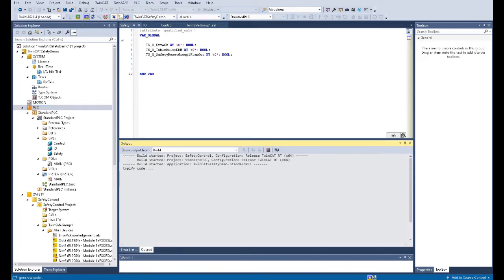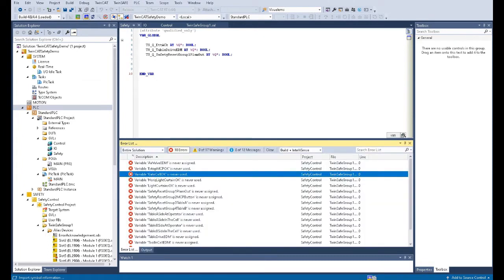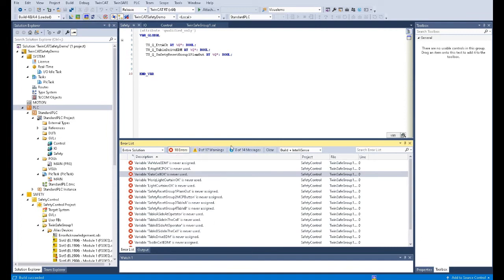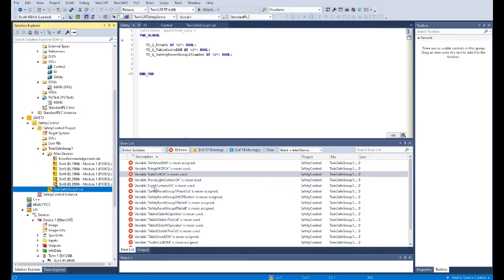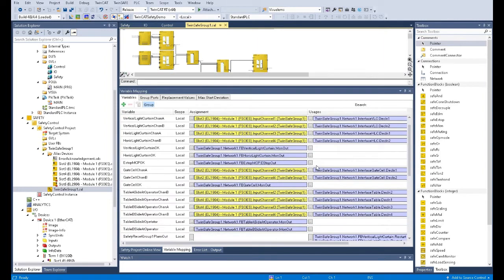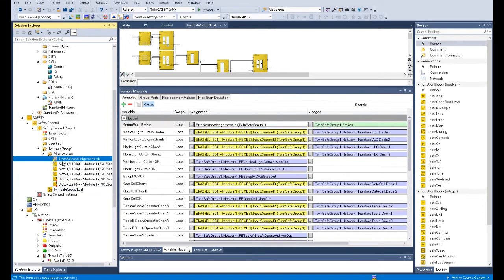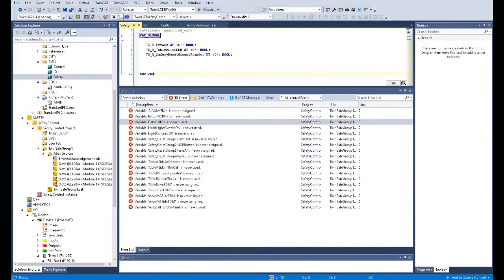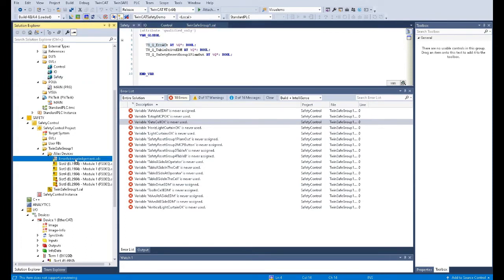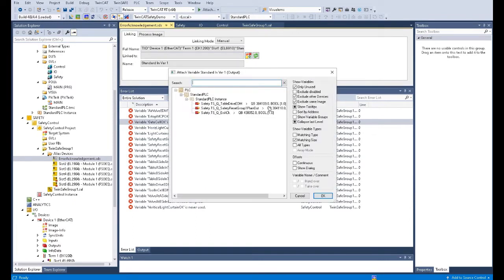After you create the tags, keep in mind you need to build your solution. This allows your system to refresh and create these tags as real tags in your system rather than text only. We don't care about errors temporarily in the safety side. So we go to our logic, and firstly let's go to this error acknowledge. This error acknowledge input has alias names here to connect the safety signal 'TS_Q.' To connect this tag, we need to double-click this alias device tag, and a pop-up shows the three tags we just created.